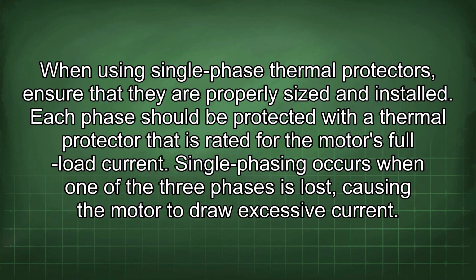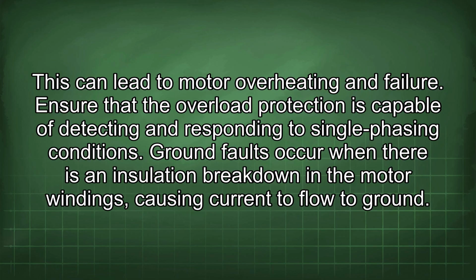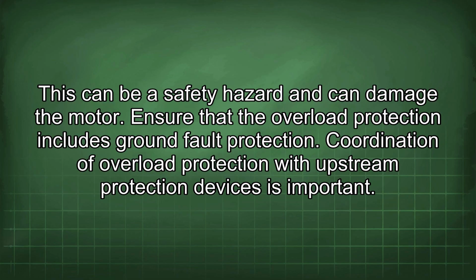Single phasing occurs when one of the three phases is lost, causing the motor to draw excessive current. This can lead to motor overheating and failure. Ensure that the overload protection is capable of detecting and responding to single phasing conditions. Ground faults occur when there is an insulation breakdown in the motor windings, causing current to flow to ground. This can be a safety hazard and can damage the motor. Ensure that the overload protection includes ground fault protection.